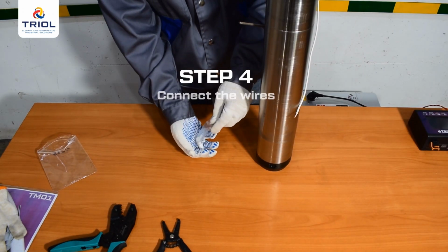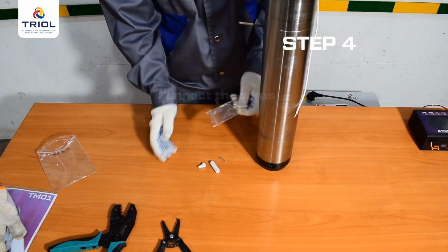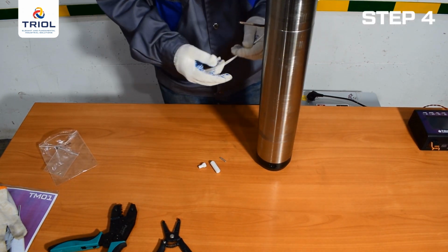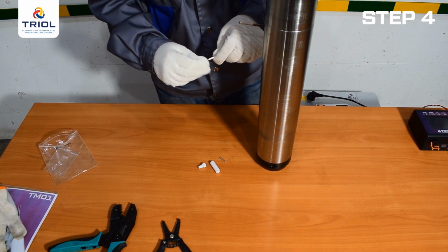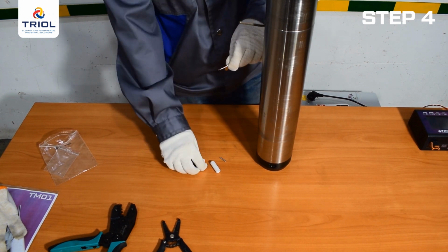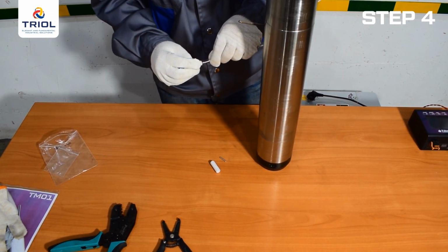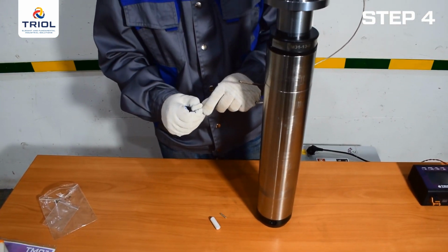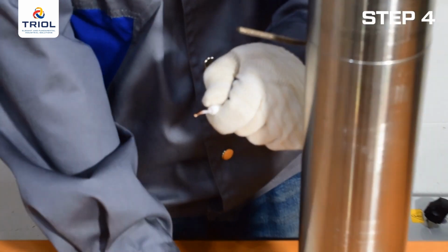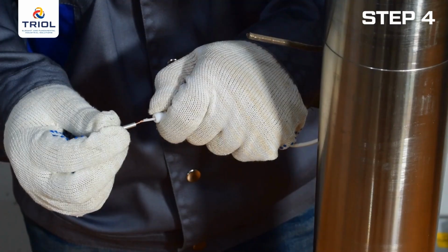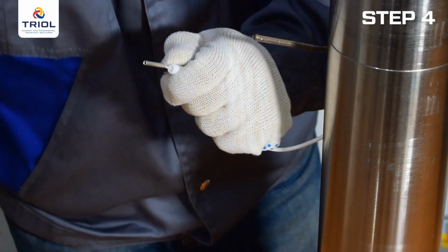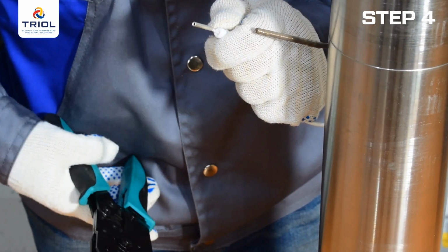Step 4. Connect the wires. Pass the 0-point wire of the TM01-10-S into the cap of the insulating container of the mounting kit until it stops in the silicone tube. Its length is calculated in such a way that when the cap rests on it, the wire is released to a sufficient length to fix it in the sleeve.